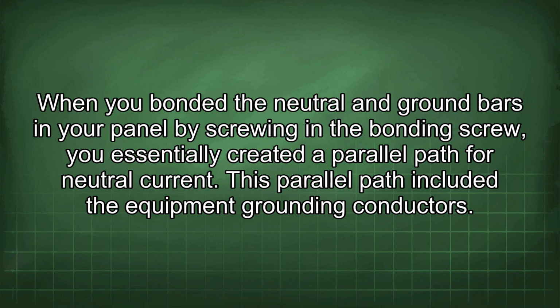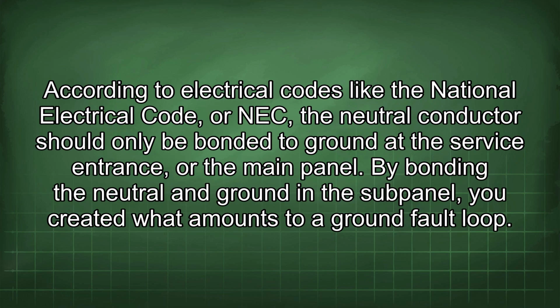When you bonded the neutral and ground bars in your panel by screwing in the bonding screw, you essentially created a parallel path for neutral current. This parallel path included the equipment grounding conductors. According to electrical codes like the National Electrical Code, or NEC, the neutral conductor should only be bonded to ground at the service entrance, or the main panel. By bonding the neutral and ground in the subpanel, you created what amounts to a ground fault loop.